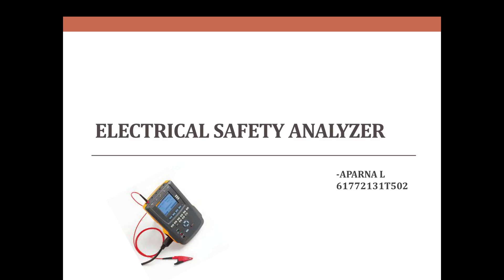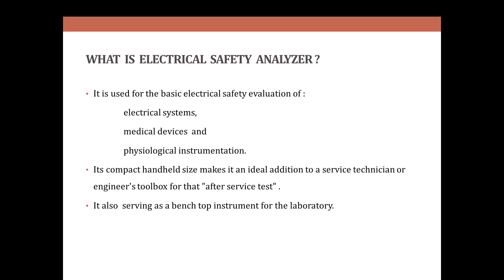Hello everyone, today I am going to take a seminar on the topic electrical safety analyzer. So what is an electrical safety analyzer? It is an instrument which is used to perform various electrical safety tests and to avoid electrical shocks to patients. It basically evaluates the electrical systems, medical devices, and physiological instrumentations.